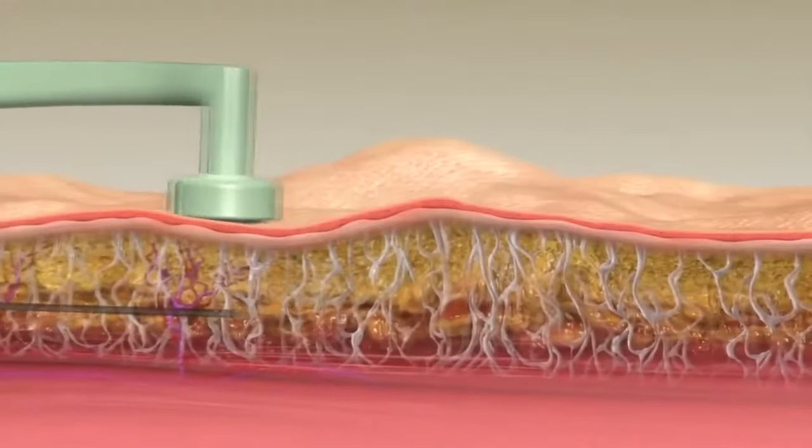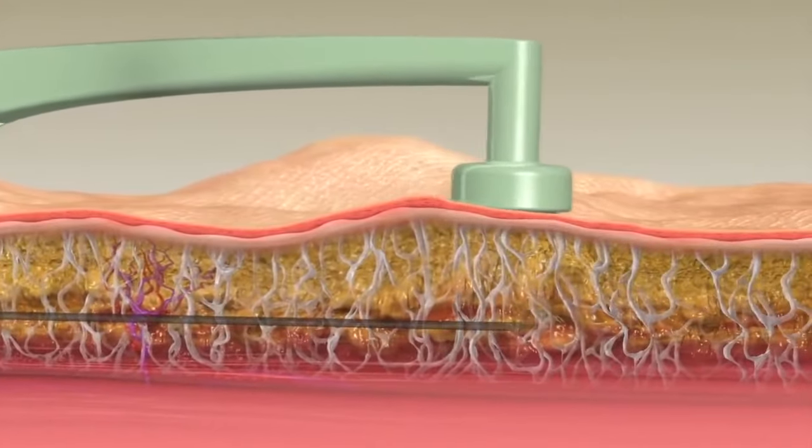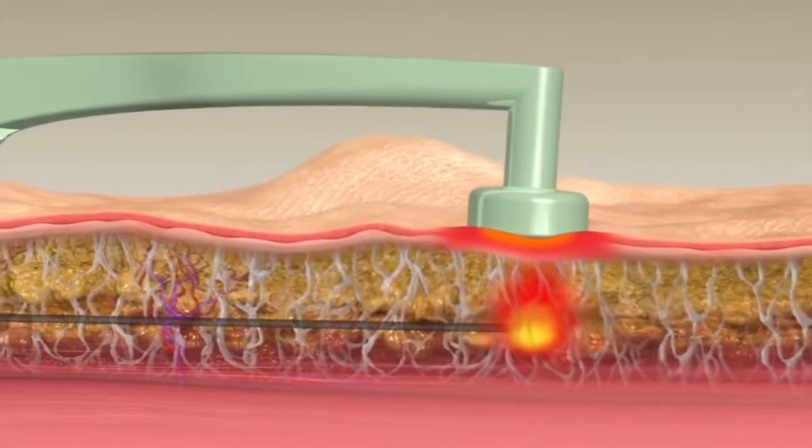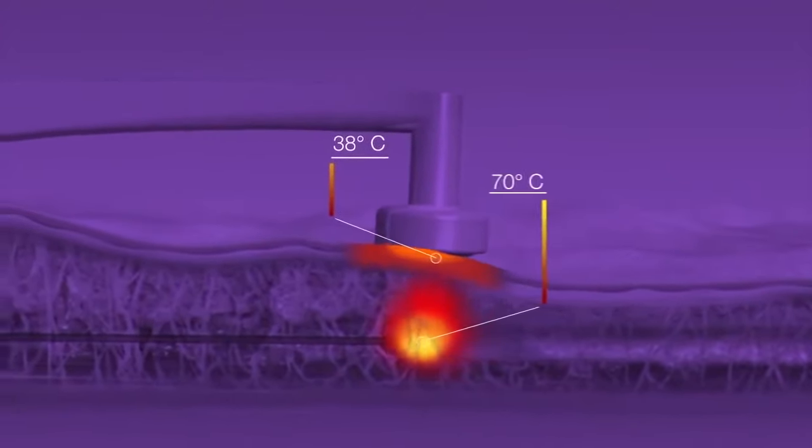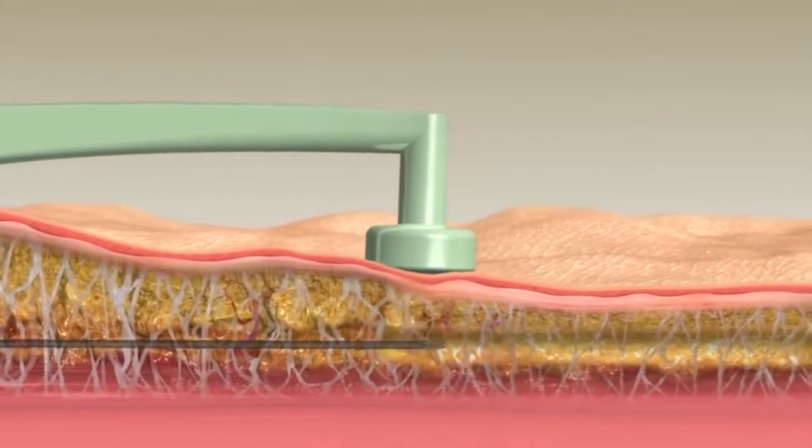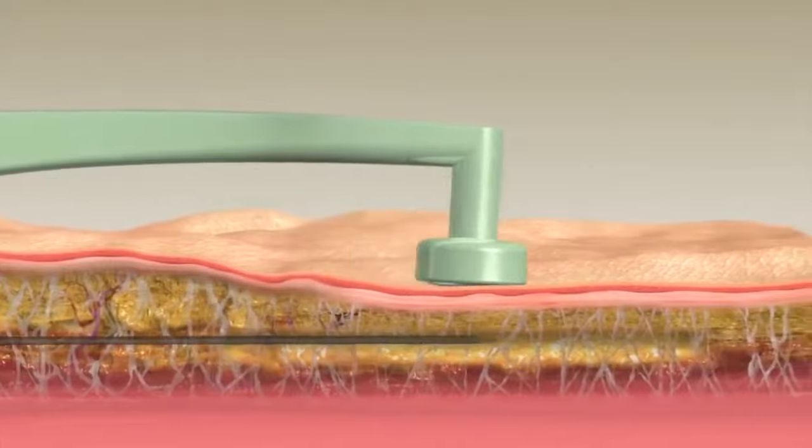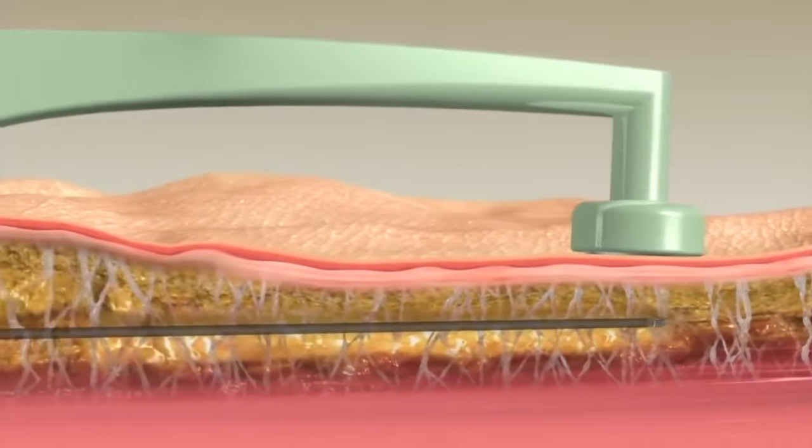The body-tight contouring procedure uses radiofrequency energy for internal fat lipolysis and external collagen contraction. RF energy flows from the internal cannula toward the external electrode placed on the skin surface. RF power is regulated based upon online measurements of skin temperature and tissue impedance.